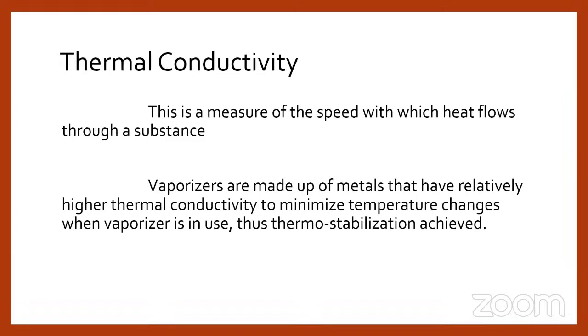And the most important part is the thermal conductivity. This is a measure of the speed with which heat flows through a substance. If you take any substance, heat will usually be transmitted from the higher heat zone to the lower heat zone, that is, from the hot zone to the cold zone. So the speed with which the heat flows is measured as thermal conductivity. Vaporizers are made of metals that have relatively high thermal conductivity to minimize the temperature changes when the vaporizer is in use.